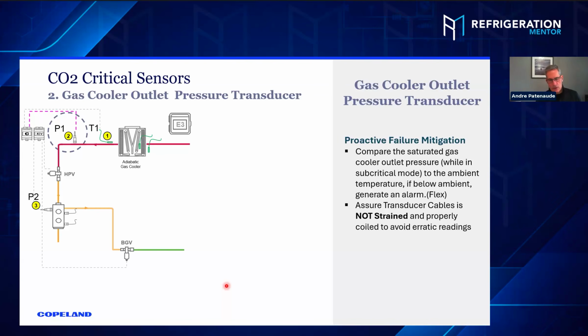So from a proactive perspective, even before anything fails, you can compare the saturated gas cooler outlet pressure, while in subcritical mode, to the ambient temperature. If it's below ambient, then you know you've got something wrong. So if this saturated condensing temperature shows a lower number than my actual air sensor, then you know you've got a disconnect somewhere. It's either this sensor or that pressure transducer, before something actually happens. It could be coming out of calibration.